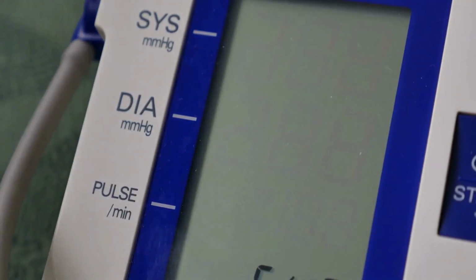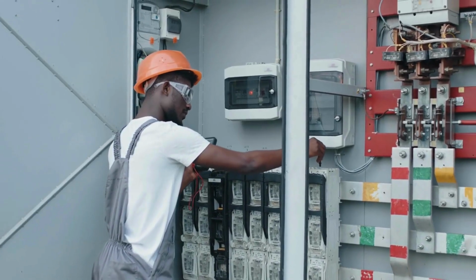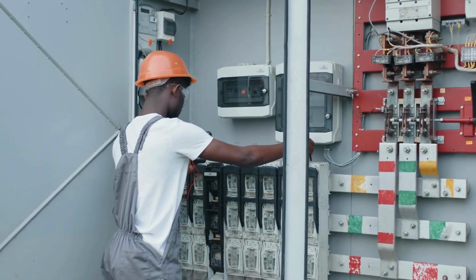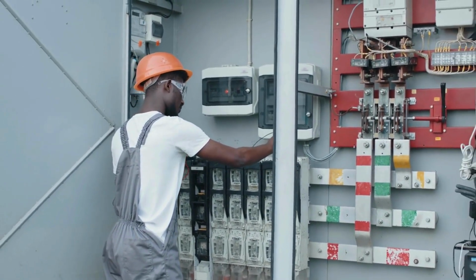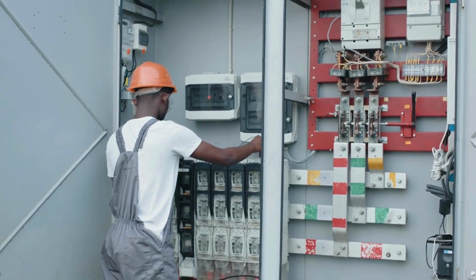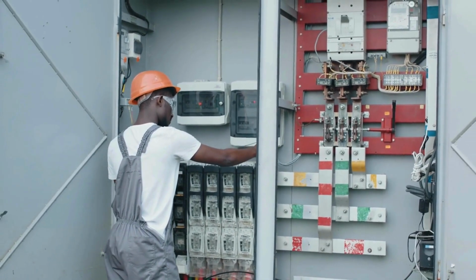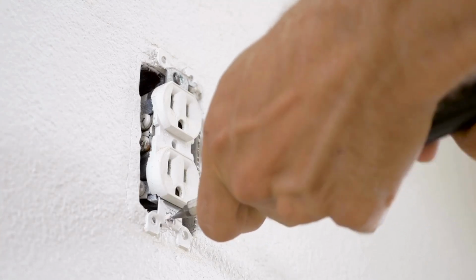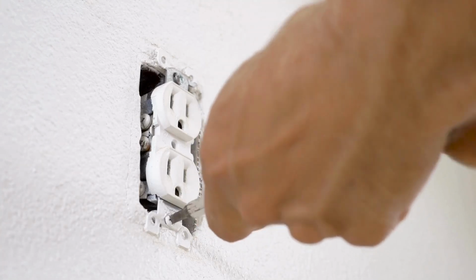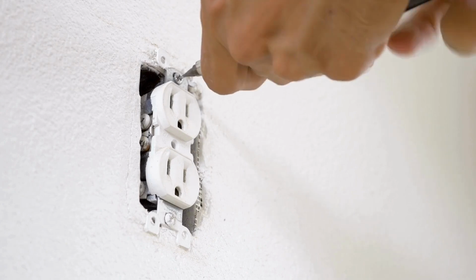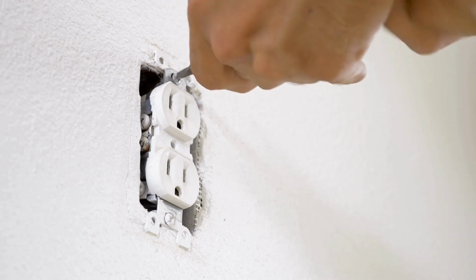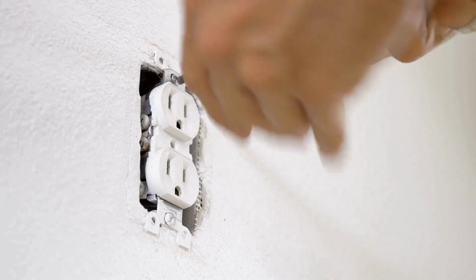Here's where electricians get into trouble. Standard voltage testers measure potential between 2 points at the moment you test them. If you're testing at a panel or disconnect, and the capacitor is downstream behind some resistance or on the DC side of a rectifier, your meter might not see that stored energy. It tells you 0 volts, and you trust it because that's what the tool is supposed to do. But it's only measuring where you put the probes, not what's waiting for you inside that enclosure.